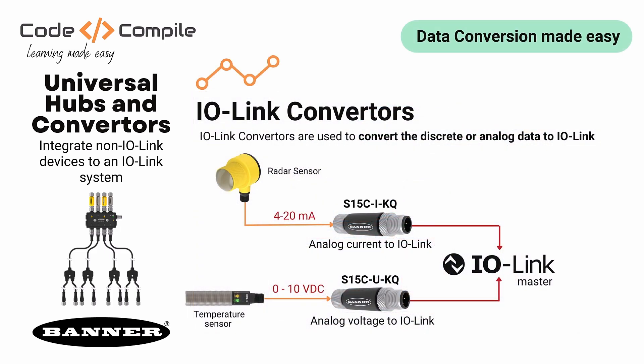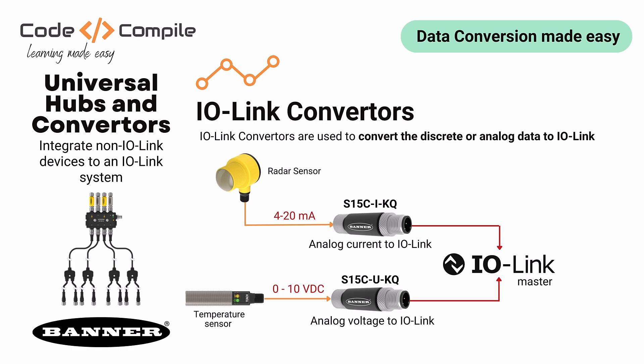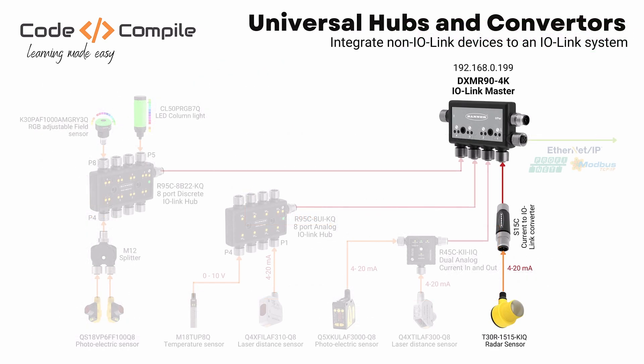Now let's talk about IO-Link converters. These converters are used to convert the discrete or analog signal to IO-Link. For this video, I will show you how to convert the 4 to 20 mA signal from a radar sensor to an IO-Link signal using a Banner IO-Link converter. This signal can be further used by any IO-Link master — for this video, we are going to use the Banner IO-Link master, the very famous DXMR90-4K.